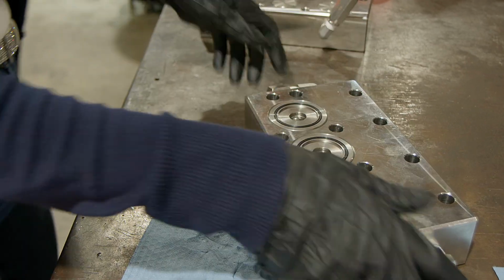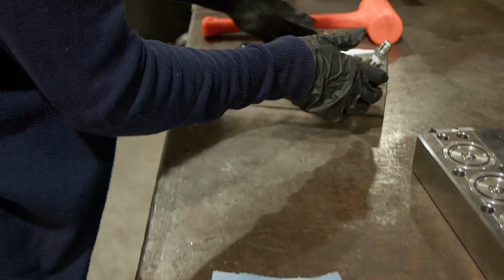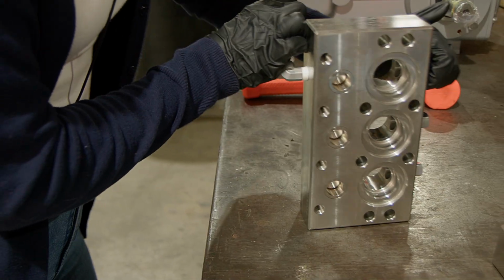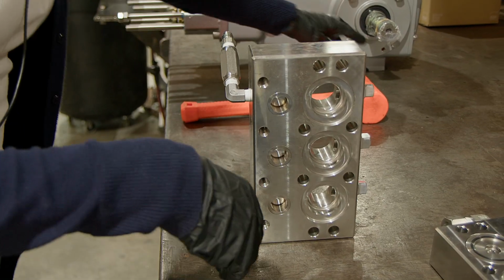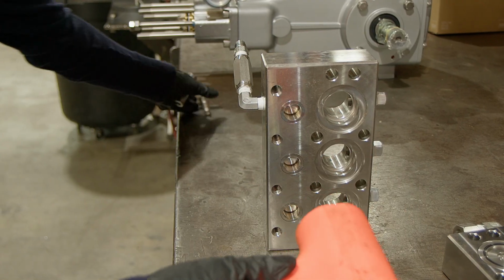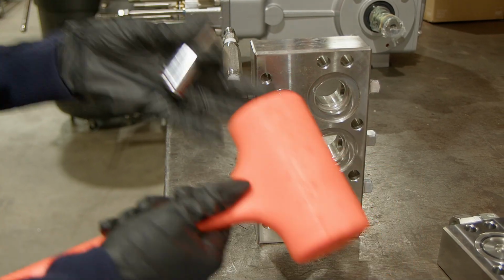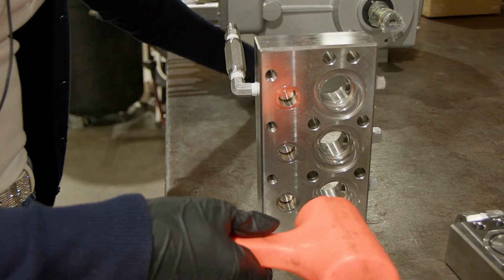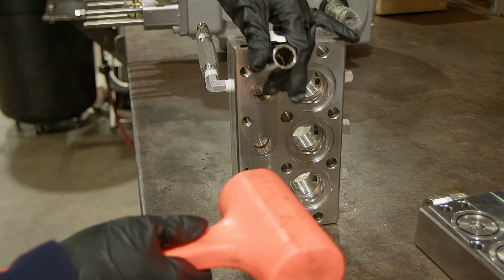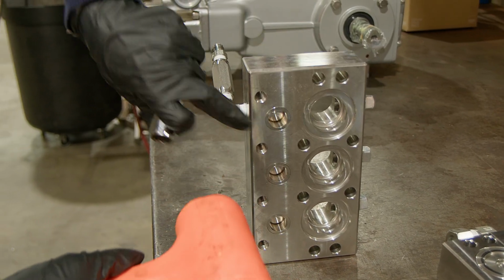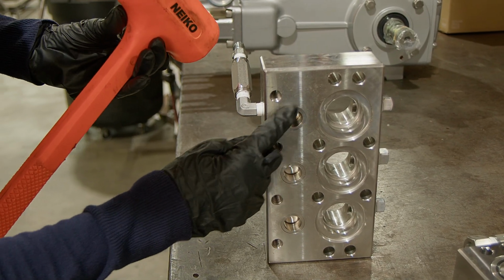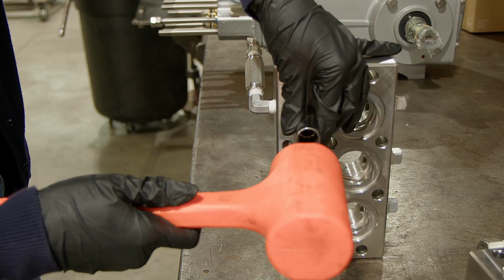On the other head, we'll put that aside for a second. On this head, to remove these valves, I'm going to use a socket and a mallet. Again, you always want to be careful with pump parts, so you don't want to use a hammer - a mallet is the best way to do this. I'm going to put the socket up against this inside ring here, and pop it out.